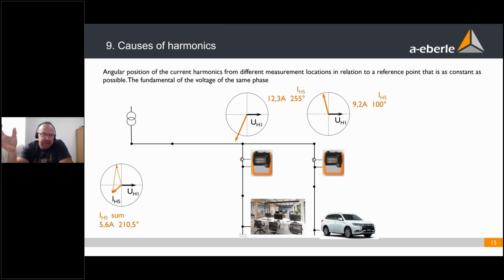To measure the reason of harmonics and who is responsible, who is producing the harmonic in your grid, is not so easy. And in our latest PQBoxes, we have many, many different possibilities to analyze the reason for harmonics in the network. One is we measure the direction, the load flow of the harmonic, but additionally, we have many, many other possibilities. So like here, we measure the fifth harmonic produced from an office. And at the office, we also have some electric charging stations. And these are also producing the fifth harmonic. But you see the phase angle of the two measurement points is in the opposite direction. So both produce the fifth harmonic, but together at the transformer, the load is much smaller than a single device is producing here.